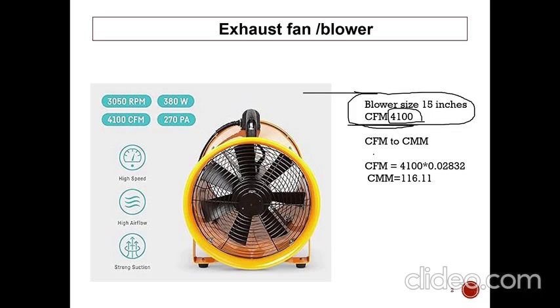To find out how long it will take to ventilate, we need to convert CFM to CMM. The CFM of the blower as given by the manufacturer is 4100. Since 1 CFM equals 0.02832 CMM, if we multiply 4100 by 0.02832, the answer is 116.11.